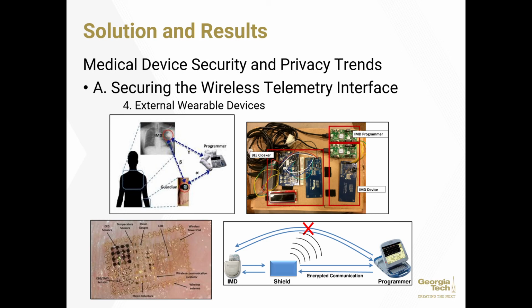Next, the use of friendly jamming to protect IMD communication, which uses jamming constructively to prevent unauthorized communication, was reviewed. Another, IMD Guard, employs an external wearable device called the Guardian to enable access control and confidential data transmissions. The Guardian first authenticates the programmer and then uses an ECG-based key agreement mechanism to authenticate itself to the IMD. Temporary keys can then be issued to allow a secure channel between the programmer and the IMD. In the event that an attacker jams the messages from the Guardian device to the IMD, the Guardian initiates an active defense by jamming all IMD transmissions.